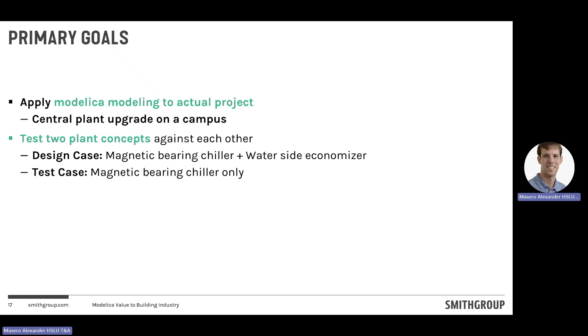This was a case where we had two different designs on a chiller plant. For anyone who doesn't know, chiller plants provide chilled water to a building in multiple ways. This was an existing large government Department of Energy site undergoing a campus renewal, looking at magnetic bearing chillers plus a water side economizer, also called free cooling, where you get cooling through the cooling tower with the compressor off. We also tested removing that option and just using the magnetic bearing chiller only.